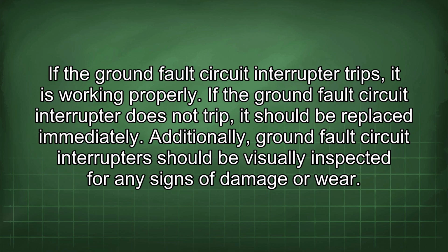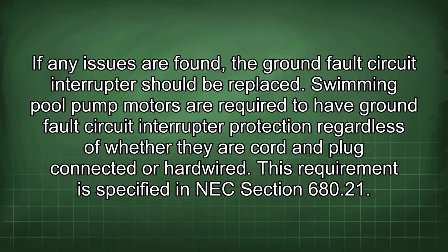If the ground fault circuit interrupter does not trip, it should be replaced immediately. Additionally, ground fault circuit interrupters should be visually inspected for any signs of damage or wear. If any issues are found, the ground fault circuit interrupter should be replaced.